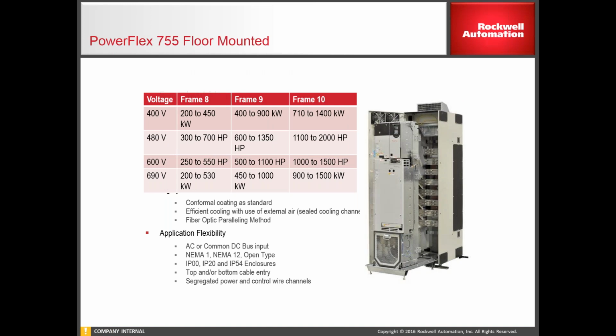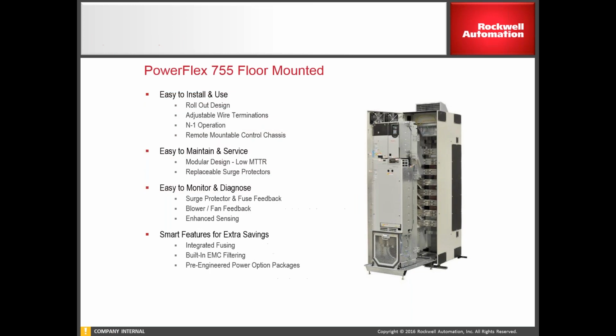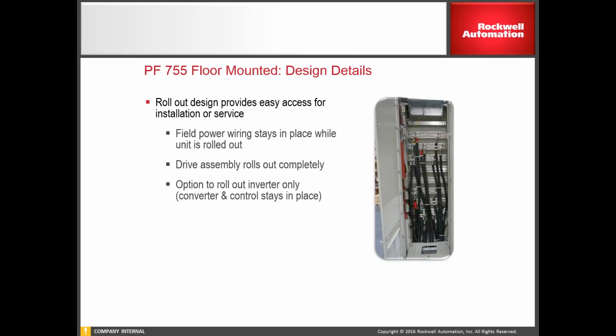So this is the floor mount 755, right? It's a roll-in feature into the enclosure. So that would be your frame. Start with the frame 8, and then with the frame 9, we would parallel 2 frame 8s, and with the frame 10, we would have 3 frame 8s in parallel to get up to the 2,000 horsepower. Another feature on the 755, the floor mount drive, is all your wiring connections are in the back of the enclosure, right? So you input power and your load cables are connected in the back. So if you had to take that drive out, you don't have to undo all those connections, right?